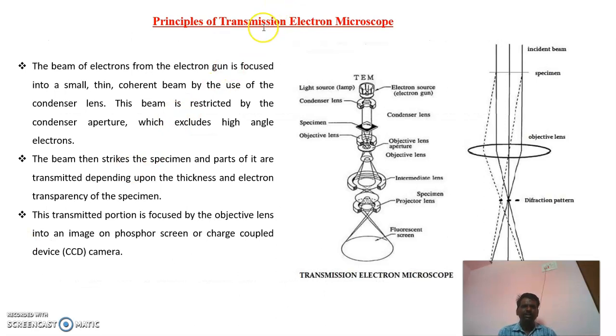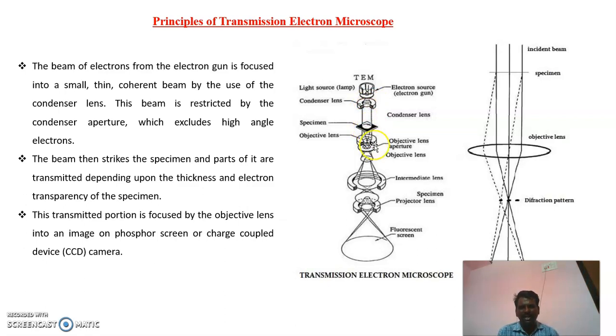Next, we are going to discuss the principles of transmission electron microscope. In TEM, the electron gun is placed at the top of the column and releases electrons. Condenser lenses focus the incoming beam towards the surface of the sample, and one portion of that incoming electron beam is transmitted through the sample. The transmission depends upon the thickness of the specimen. The transmitted electrons are focused by the objective lens, and the objective aperture filters the highly diffracted electrons, enhancing the contrast of the transmitted electron beam.